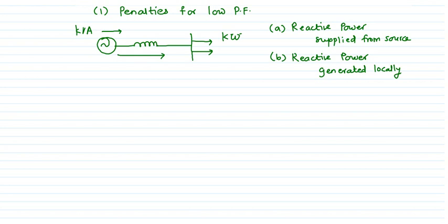Reactive power is required for the existence of an electrical field, like electromagnetic actions. Reactive power is required for the induction motor and its working principle. But what we get at the end, our use, is always in terms of active power. That is why, from the distribution company side, if you are utilizing energy at a lower power factor, it is considered a sign of low-efficiency utilization of electricity.